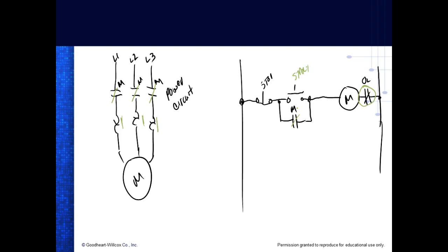So the only thing allowed between the load and L2 is the overloads for a motor starter, nothing else is allowed between L1 and the load, or between L2 and the load. Do you all understand that?